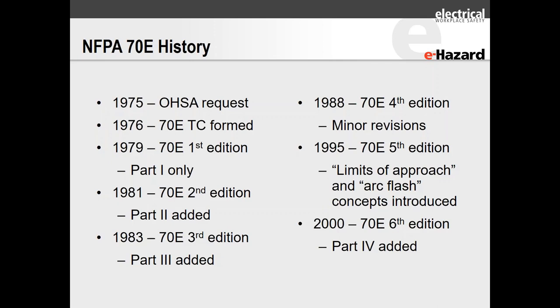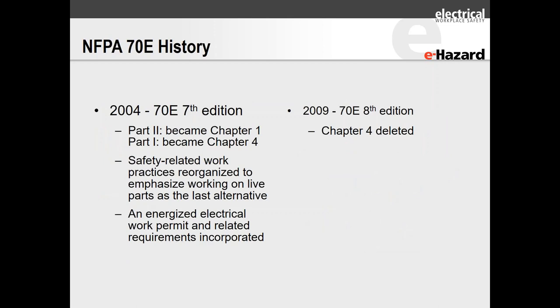In 1995, it really started to take on more value. Limits of approach and arc flash concepts were introduced — it was becoming evident that arc flash energies needed to be taken far more seriously. In 2000, part four was added. In 2004, it was a really valuable edition: parts were reorganized, and safety-related work practices were reorganized to emphasize working on live or energized parts as a last alternative, which remains one of the most important tenets of 70E — working in a de-energized state. An energized electrical work permit and related requirements were incorporated in 2004.